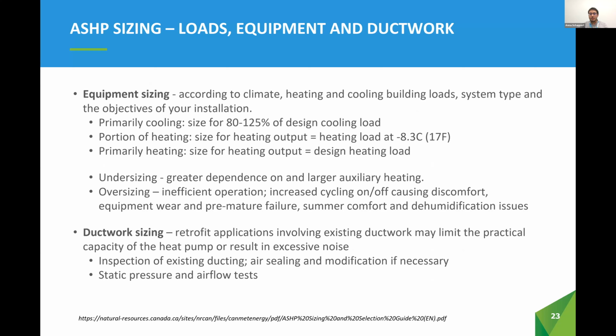In retrofit applications of centrally ducted air source heat pumps, the maximum size of the air source heat pump may be limited by the maximum airflow capacity of the existing ductwork. Air source heat pumps provide lower supply air temperatures, which require more airflow to meet the same heating load when compared with a traditional furnace.